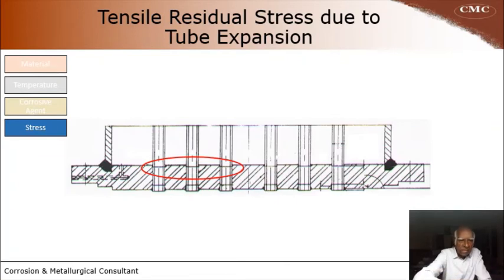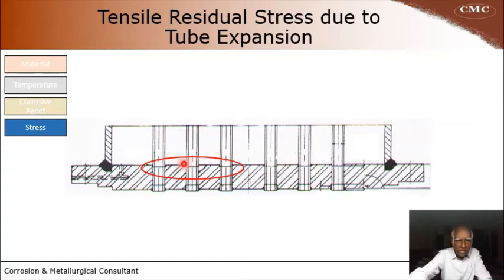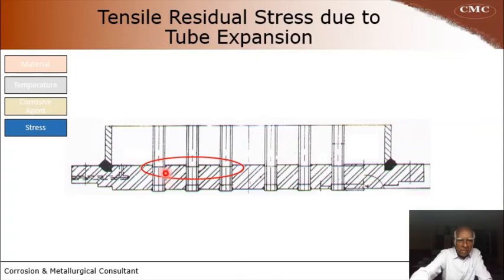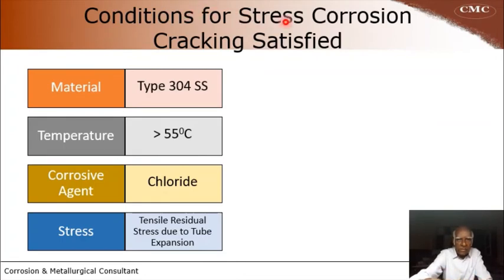The last condition is stress. Since the term is stress corrosion cracking, there must be a tensile stress. All the cracking occurred just about 5 mm above the tube sheet. When heat exchangers are fabricated, the tubes are expanded into the tube sheet hole so that they remain tight with no crevice. This expansion sometimes goes beyond the length of the tube sheet, which is why the cracks occurred just beyond that point — above this there is no stress. So all four conditions are satisfied.